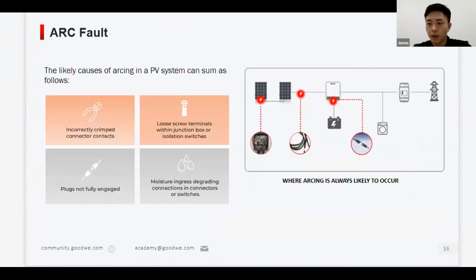The first topic I want to talk about is the arc fault. In the discussion about arc faults in PV systems, the DC side is always the focus, because AC voltage turns around and goes through the 0 point 100 times per second, so the arc extinguishes itself. But on the DC side, it always remains at a continuous voltage. If there's a damaged cable or incorrect connector contacts, or if the plug is not fully engaged, the high voltage could jump through the air and cause fire. Once the arc has been established, it tends to support its continuation because of the continuous high voltage, and it could cause a fire.